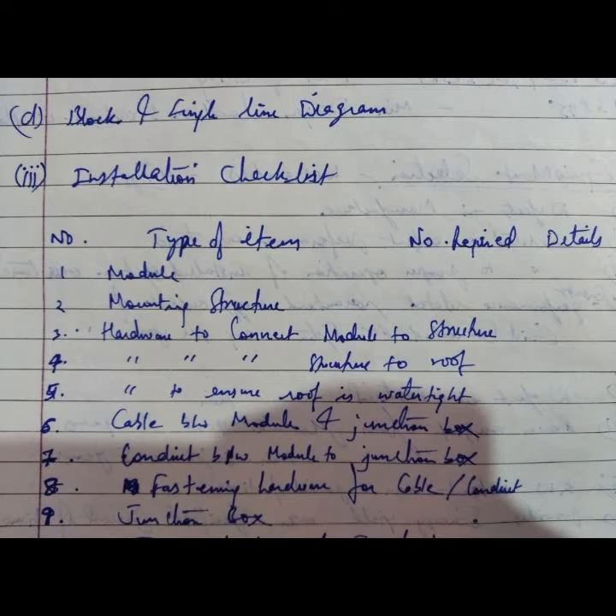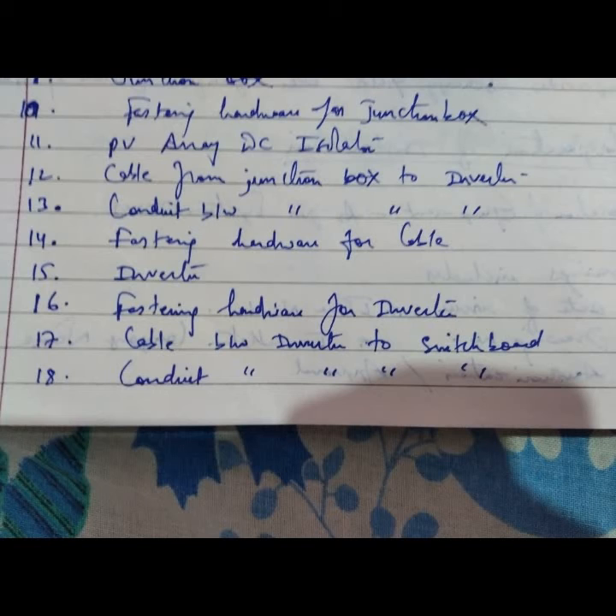In this, for each item we require the number and details: which company, sizes, and in what quantity, like that. First, modules: how many modules are required; mounting structure: how many are required, like details; hardware to connect module to structure, hardware to connect structure to roof, and hardware to ensure the roof is watertight, so water should not go inside the roof. Cable between module and junction box, conduit between module and junction box, fastening hardware for cable and conduit, and junction box; array monitoring box comes in the array junction box category.